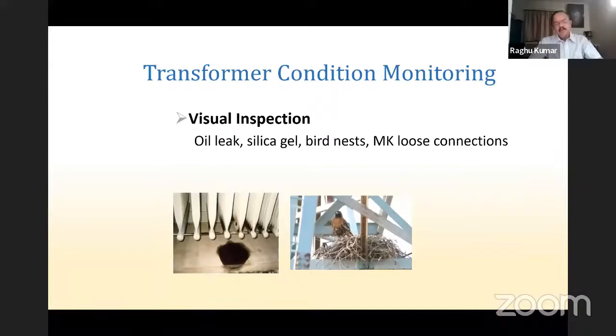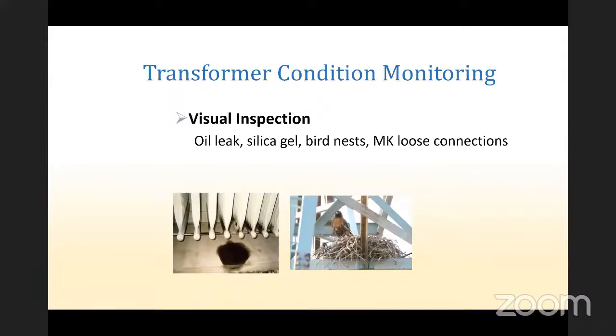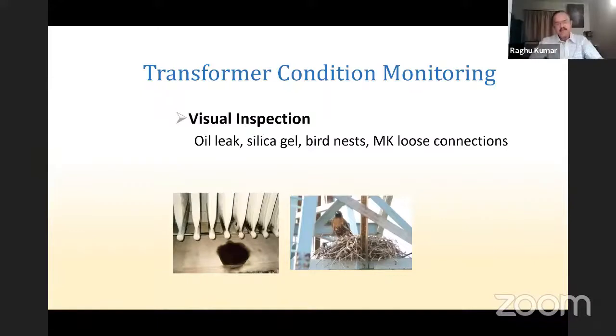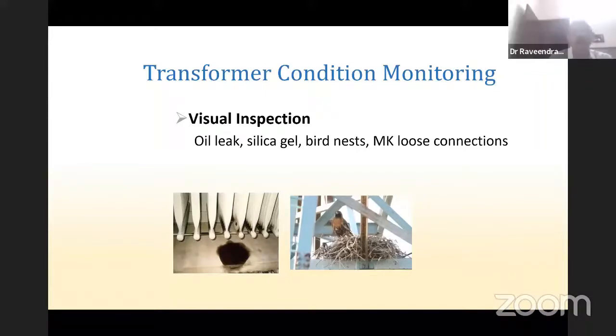And this bushing was not an external bushing. This bushing was going inside a GIS. So a failure could have damaged not only the bushing, but even the GIS compartment could have been damaged, and it would have been a major disaster, and it would have taken more than a year to repair and replace. Just because the visual inspection identified the problem, immediate action could be taken. The bushing was replaced, and the transformer was brought back into service.